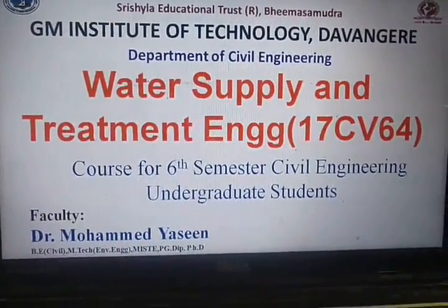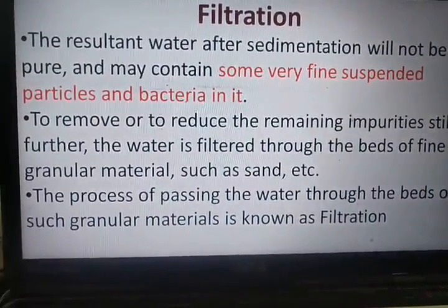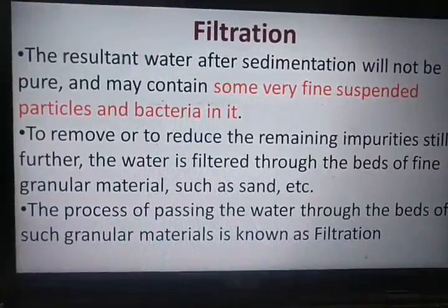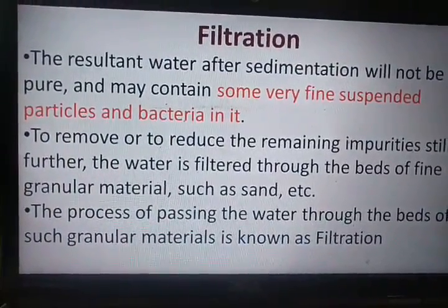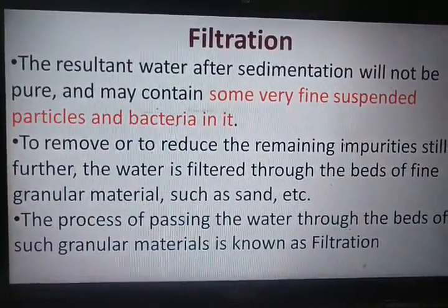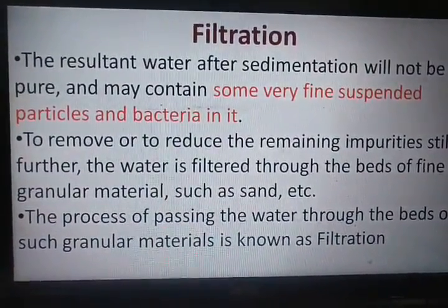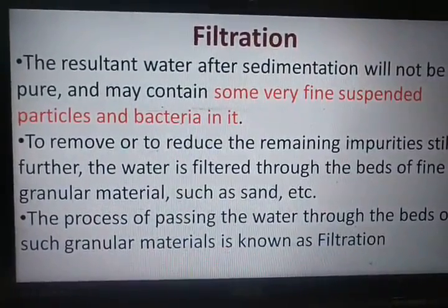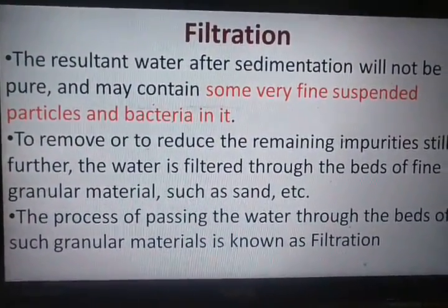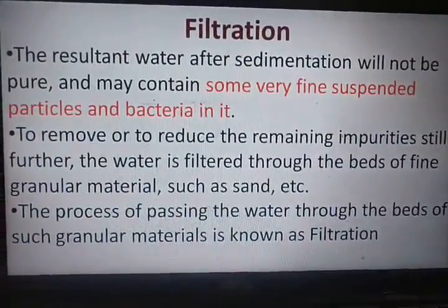Filtration is done after the sedimentation process. As you know, in sedimentation we might have removed some bigger solids, which could easily settle with the help of gravity. Whereas water may still contain some very finely suspended impurities, and also some bacteria. To reduce the remaining impurities, we have to pass the water through beds of filter material.